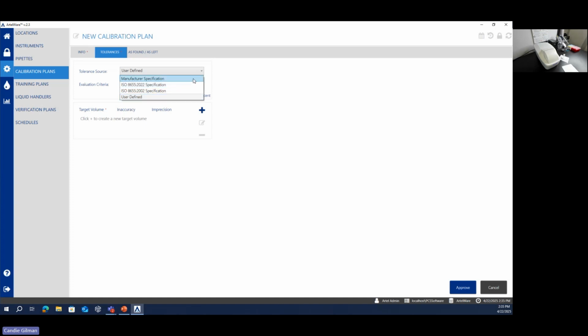If you select manufacturer ISO tolerances, you then see this little multiplier box come up in case you wanted to multiply those tolerances. But for today, I have a user-defined tolerance that I'm going to apply. So next I need to make a decision. What are the things that I'm evaluating? Am I evaluating inaccuracy or imprecision, or both? And for pipette calibration, I'm going to select both. I'm interested in both of these statistics.